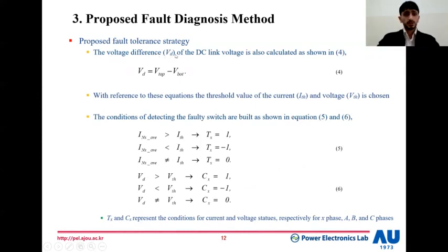The voltage difference, V_D, represents the voltage difference between the voltage of the upper and lower capacitors of the DC-link voltage, as shown in equation number four. And then we set threshold values for the current and voltage to be compared with. The main conditions are represented in equation number five and six, as shown here. The conditions for the current are labeled by T and C for the voltage. X, again, represents the phase A, B, or C.